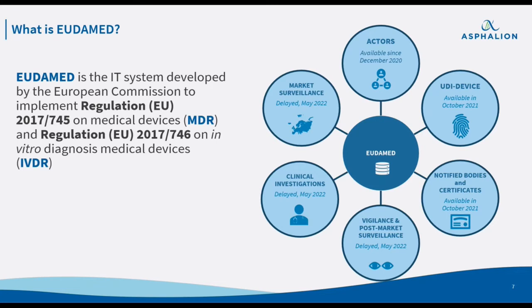EUDAMED is divided into a total of 6 interconnected modules, namely, as you can see in this feature: Module 1, the actor registration module, in which all economic operators are identified. Next, we have the UDI device module, Module 2, in which the key characteristics of the device family or each medical device are included. Then we also have Module 3, the module for notified bodies and certificates, where notified bodies are able to register themselves as such, and also upload all the certificates issued by them.